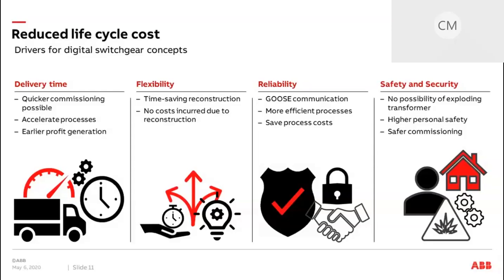Furthermore, sensors are very flexible. Digital switchgear can adapt to the requirements in the network when they change over time. For example, the feeder current. So you could use a 2000 amp feeder also for 600 or 1250 amps and just adjust the software in your relay rather than exchanging the CTs and still measure it correctly.